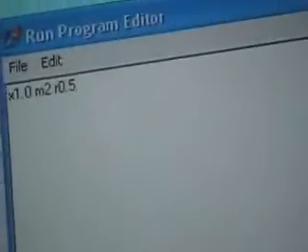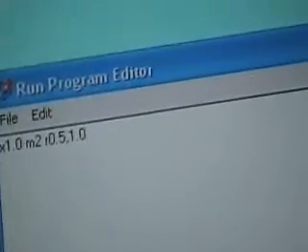And then I want to put the ramp command in. So I might want to ramp from 0 up to, let's say, 0.5 volts, and I want to do that in half an hour or whatever like that. So I want to go 1.0 volts per hour, so we get up to 0.5 volts.